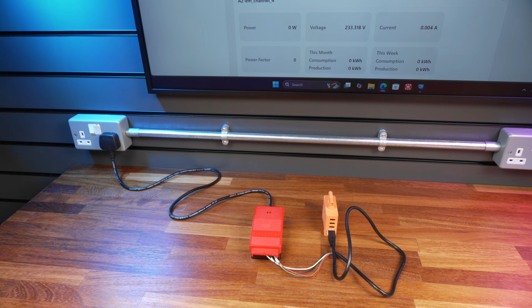And the reason that this is important is that, at least in the UK, on a domestic energy tariff, we are billed for real power usage in watts, not apparent power. This does vary between countries, and even in the UK some commercial energy tariffs will bill for reactive power in addition to real power. But if you want to keep track of the power you're actually being billed for, it's important to have an energy monitor that can monitor the real power and not just the current. And it's also important to make sure that the device you're using is definitely calculating the real power properly and not just multiplying the voltage by the current and calling it watts.